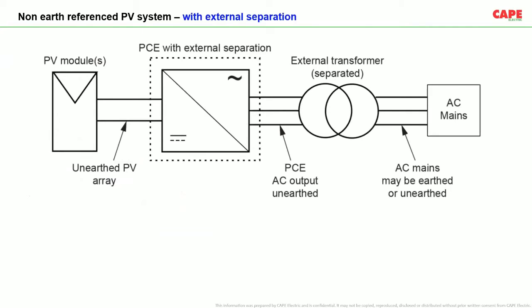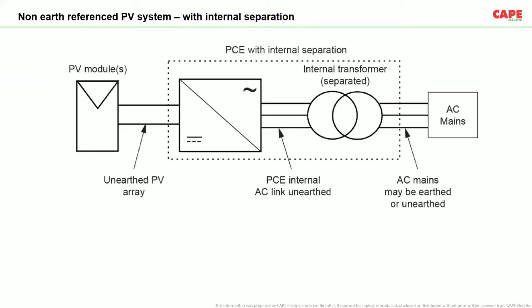The second type of system is the non-earth referenced PV system. Non-earth referenced PV system means it's completely floating. You need to have an insulation monitoring device, and there are certain insulation levels applied. If the insulation level is lesser than the recommended limit, it's very easy. You can find out and take the necessary step. So that is the second one, the non-earth referenced PV system.